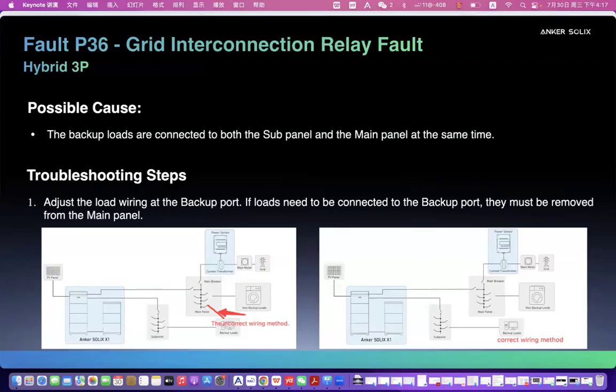Next is P36. It's a grid interconnection relay fault. So when will this issue happen? I think this diagram shows it clearly. You should connect the backup loads to the backup port. Do not connect them together with the non-backup loads, or it will create a circuit and cause bad things to your backup loads, and affect normal use. Just adjust the load wiring at the backup port, and make sure it is removed from the main panel. And if it happens, try to restart the machine again. Sometimes it will solve it, if you are sure the wiring is right.